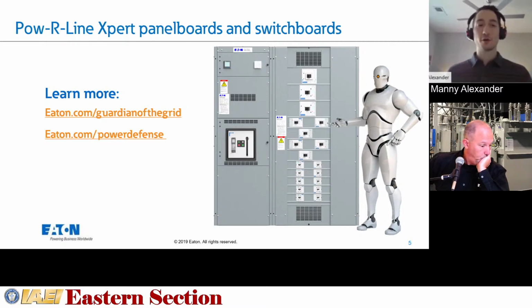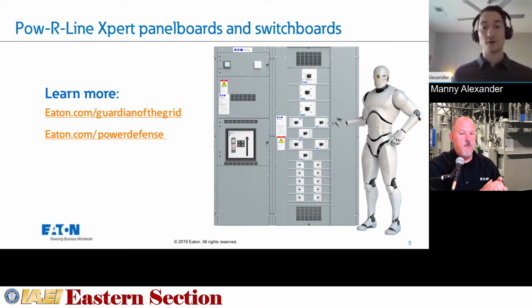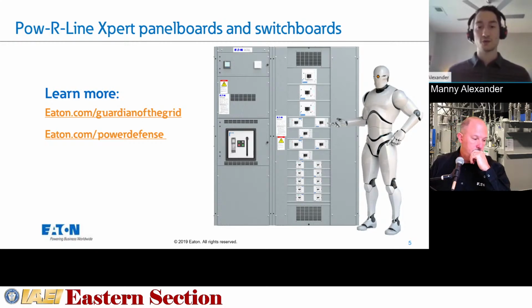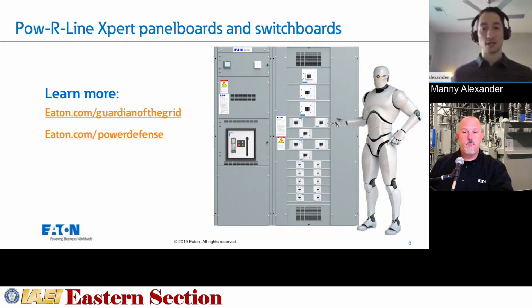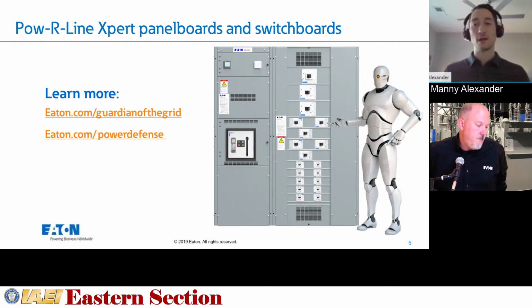Yeah, the smallest frame breaker that we use in the Power Defense molded case offering is the Power Defense frame size 2. And that frame size 2 is basically a 225 amp molded case breaker. So you could get ground fault protection with that 225 amp breaker. You could get ARMS functionality across the board on all of the molded case breakers from the PD2 up through our 1600 amp Power Defense frame 6. And you could get those in the same trip unit. So you might have an LSIG trip unit with ARMS functionality.